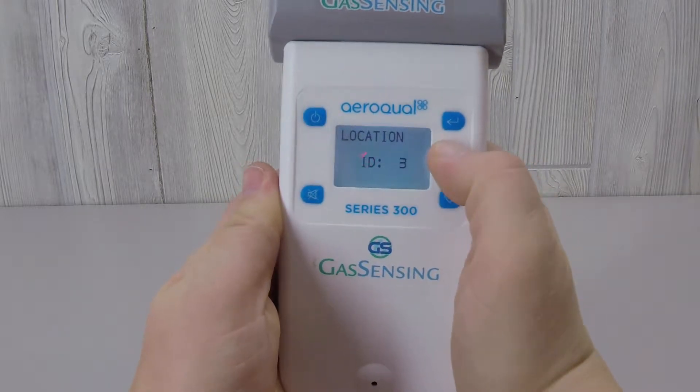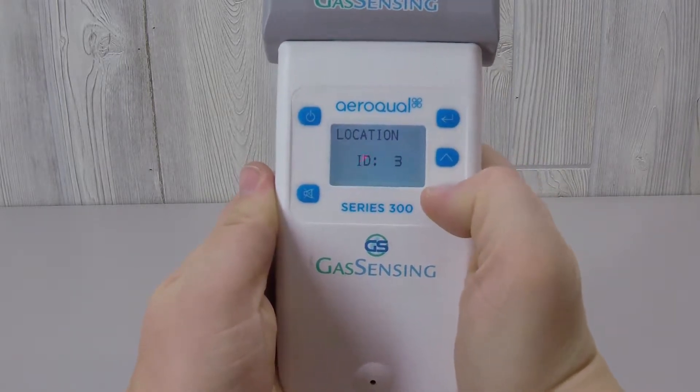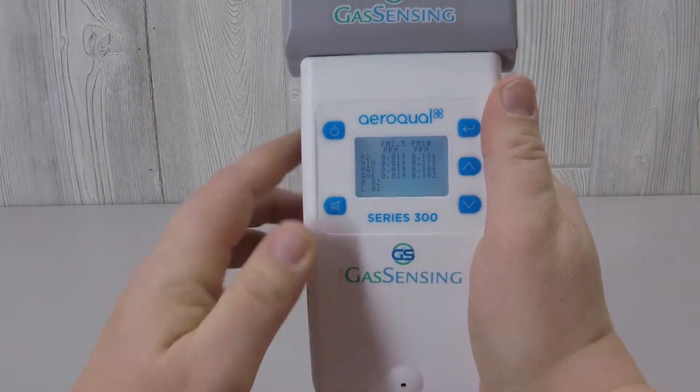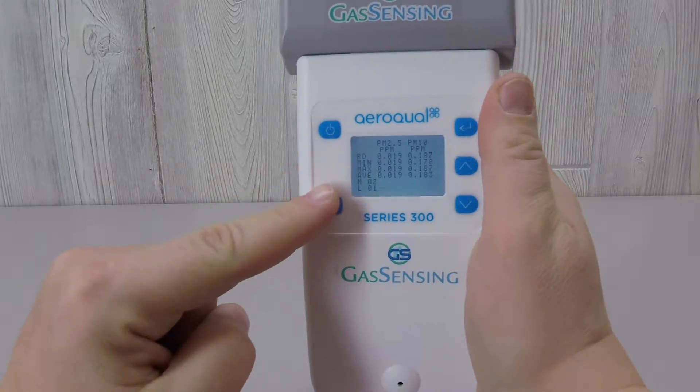The first menu item, Location ID, would typically not be used with the S300. Selecting the min, max, average menu item causes the word 'start' to appear. When you return to the screen readout, you can see that the minimum, maximum, and average readings now appear, while the current reading is still listed at the top of the screen.